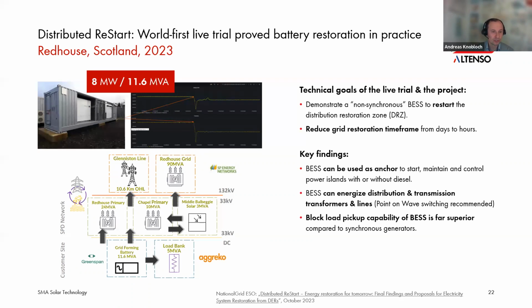The key findings were that battery energy storage systems can be used as an anchor to start, maintain, and control power islands with or without diesel, and that battery energy storage can also energize distribution and transmission transformers and power lines. An interesting observation was that point-on-wave switching was recommended to avoid some oscillations. And the block load pickup capability of battery energy storage systems is far superior compared to synchronous generators, because battery energy storage systems can pick up to 100% of the load, while conventional generators are typically only capable of picking up 10 to 50%. Read everything in the report, which is available now.